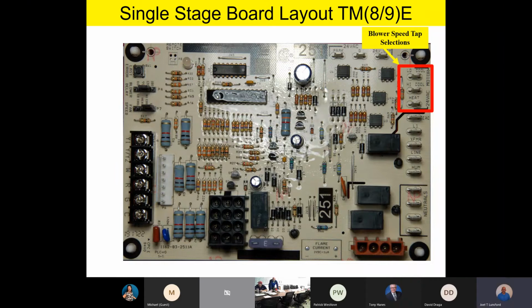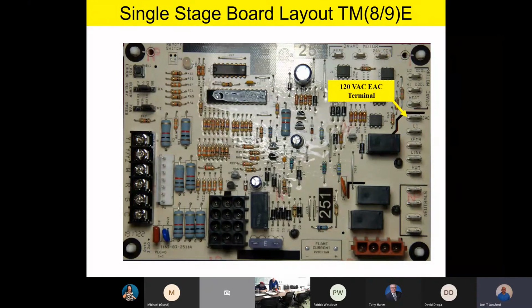Everybody good? Okay. Well, team, as we come down the side of the board, you'll notice there's going to be an EAC terminal. This EAC terminal is 120 volt output for an electronic air cleaner. Anytime the fan is running, this EAC terminal will be energized with 120 volts, and you can use that to power an electronic air cleaner.